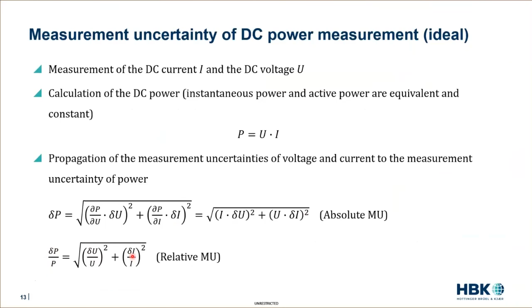But this is, of course, nice and important, and it's also useful to do this in the first step, because if you think about electric drive applications, the electric machine represents a high inductive load. Therefore, the currents are more or less sinusoidal, as we saw in the measurements before. And for this reason, most of the active power is transferred in the fundamental. And if you know the measurement uncertainty of the fundamental, that's a good estimate to guess how big the overall measurement uncertainty of the total power could be.